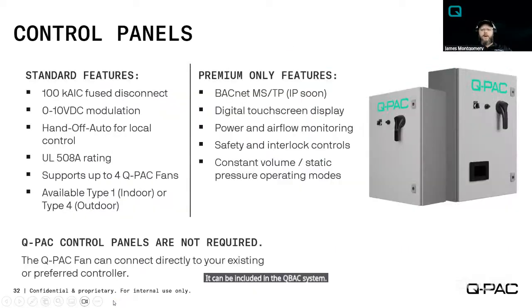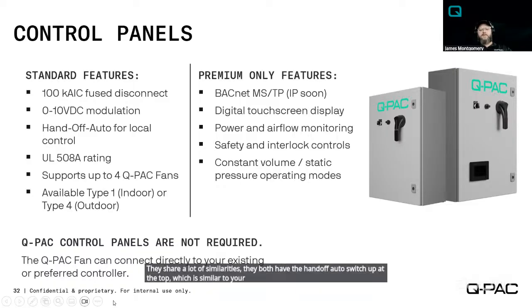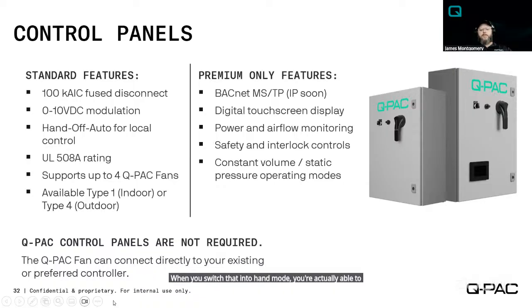There's our control panel. If you can see those on the left, that's the basic, no HMI, no touchscreen. The one on the right, that's the premium. They share a lot of similarities. They both have the hand-off-auto switch up at the top, which is similar to your bypass that you've heard of on a VFD. But in this case, when you switch that into hand mode, you're actually able to turn the potentiometer, the dial there, and you're able to set the speed of the fan.